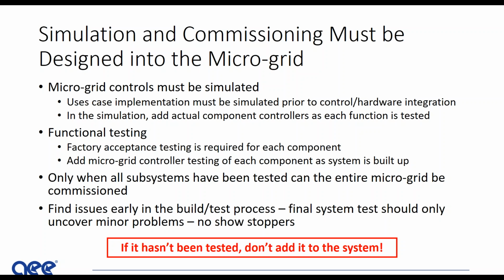As you build up each part of the components, each part of the hardware and software together, you're building up a system. Always start at the lowest possible subsystem and build up from there. Never add to that lowest subsystem until it's 100% checked out. Only when all subsystems have been tested and cleared can the entire microgrid be tested.